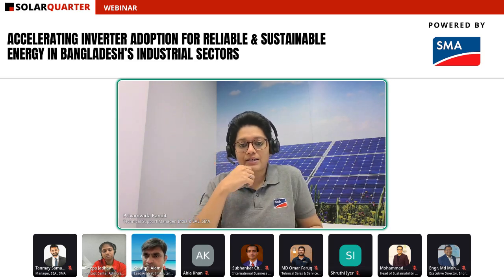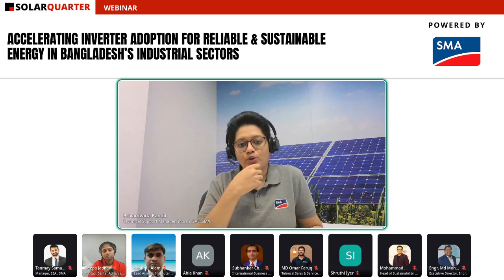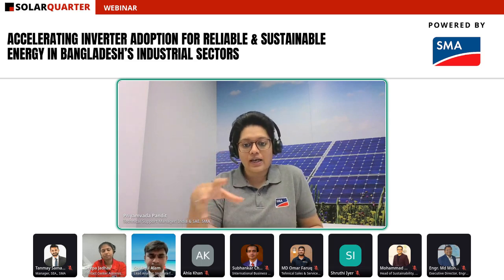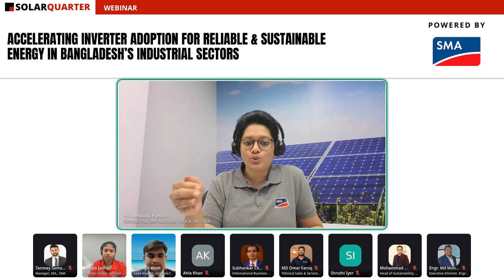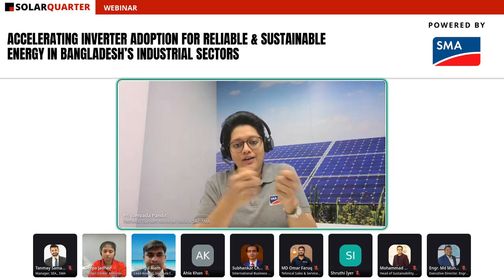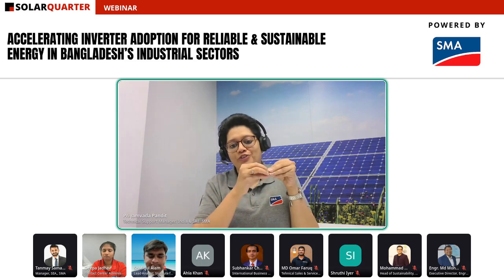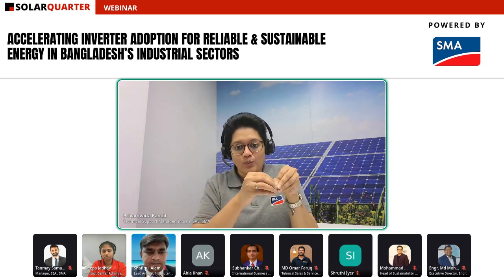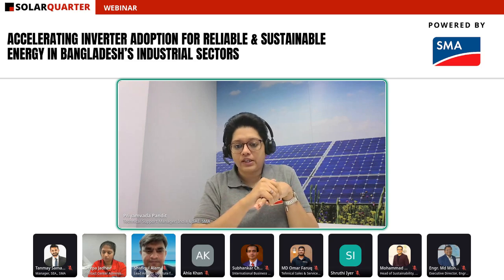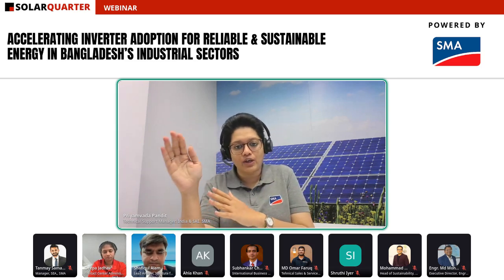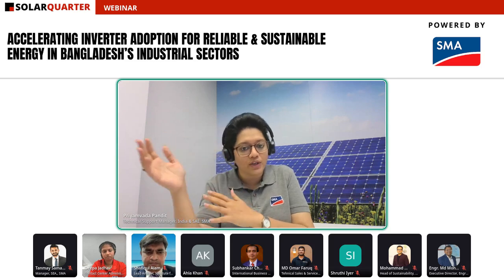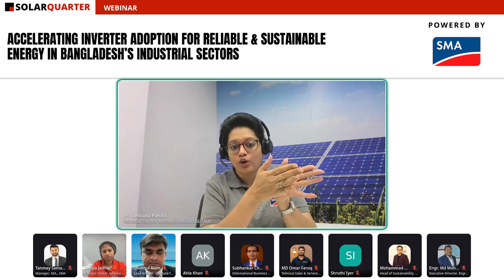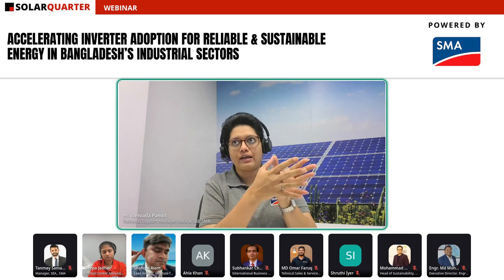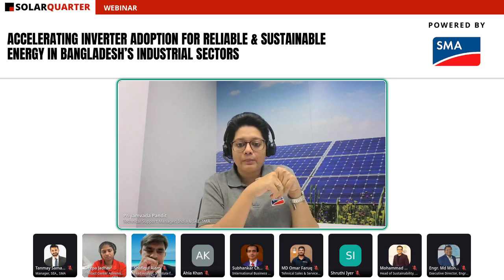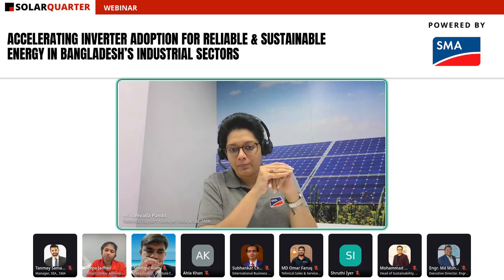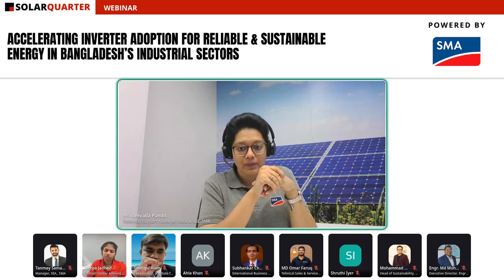So to avoid that, it is important that your PV system should also be able to support you with reactive power. Inverters currently available are very much able to do that. You just need to enable or unlock the specific parameters of the inverter, and the capacity of the inverter matters. This becomes very important, especially in the industrial sector. In pure utility, where you don't have many local loads and are exporting all the power, or even in residential, where loads don't consume reactive power that intensively, you typically don't see this problem. But in the industrial sector, this is a very big problem.